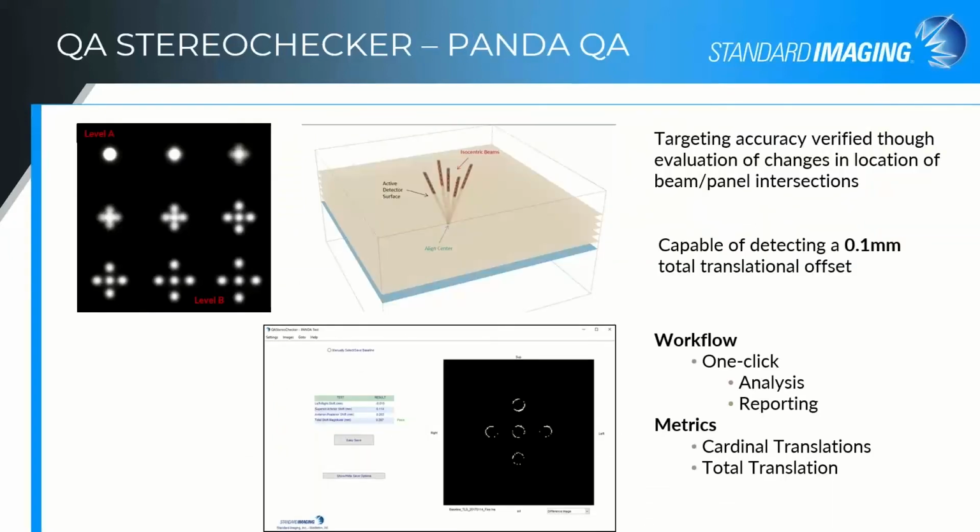The Panda test, which replaces the AQA test, if you're familiar with that, has you create a field where your target center is actually below the plane where we're measuring. So if you do 5 fields from these different angles, all targeting that center alignment point, the slice that we get through here is very sensitive to the positioning and the angle of those beams.